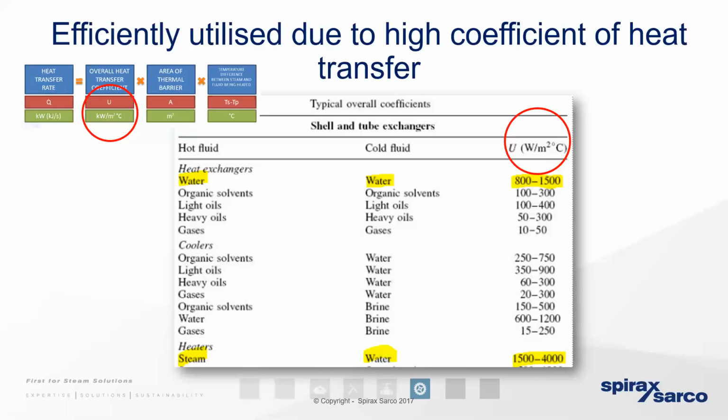Now, traditionally, steam or hot water was generated from steam relatively slowly over a period of time. And that meant that any hot water that was produced had to be held in storage in a buffer vessel on the secondary side. But now we can harness all the attractive qualities that are present in steam to generate hot water or other processed fluids instantaneously and on demand, meaning we can eradicate that buffer vessel altogether.